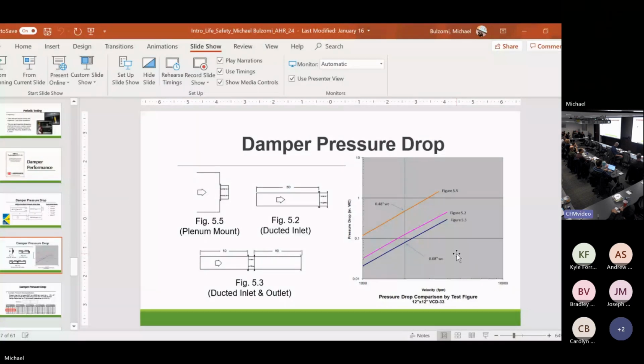When you compare the AMCA figures, if we look at the AMCA pressure drop figures, and it's got a 12 by 12, 24 by 24, 36 by 36, all those AMCA pressure drop figures are the nutritional facts on the back of a cereal box. So I can look at all my cereals in a row and go, I'm a health conscious guy, I like to eat low carb, which has the lowest carb? I'm going to pick that one. All that is doing is letting me put every damper manufacturer side by side with AMCA ratings and go, they have the lowest pressure drop on a 24 by 24. I want that one. It's really misleading.